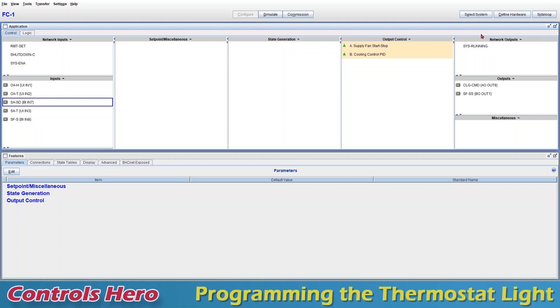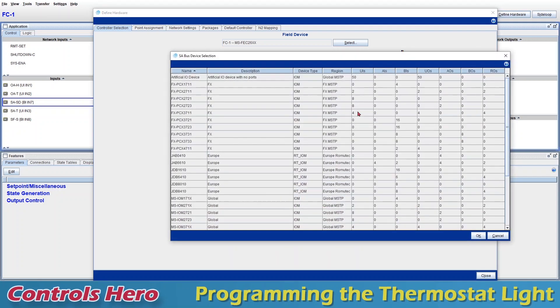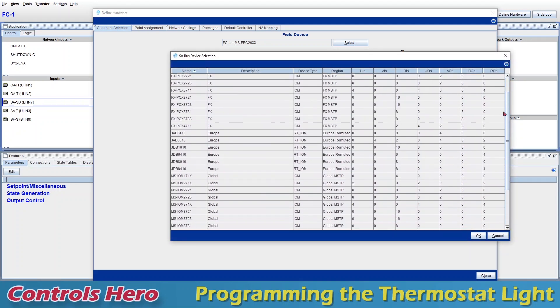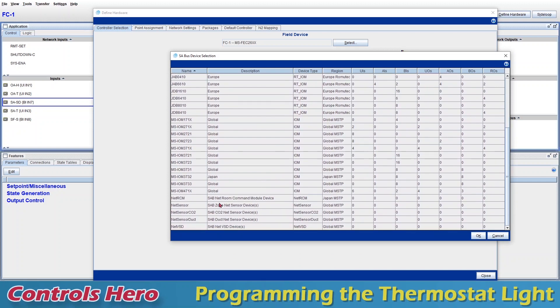Now let's go back to define hardware. I'm going to add a device, an SA bus device, add device, and I want to look for a network sensor or net sensor. We have three types. We don't want a CO2, we don't want a duct sensor, so we want a room temperature sensor or a zone net sensor, which is this one. I'm just going to click OK.